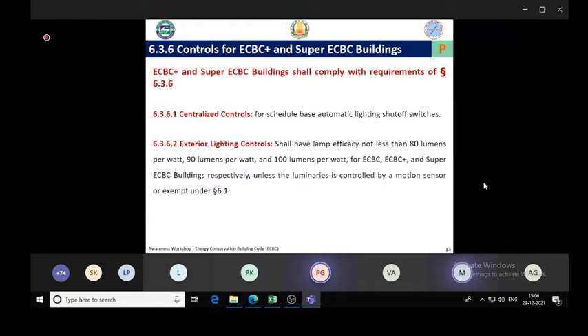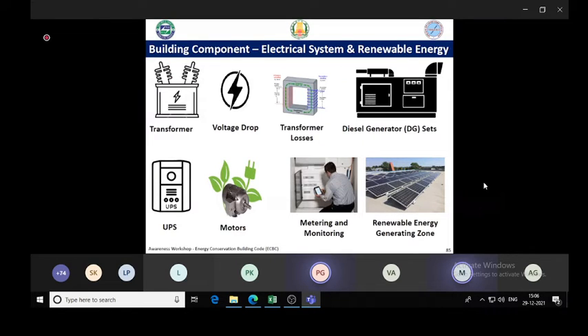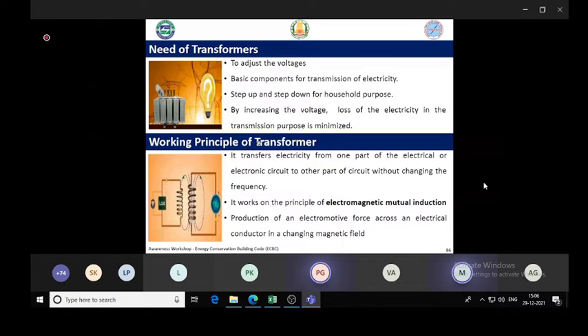Okay, so that was about the lighting section, and now the electrical section. In the electrical section, all of the requirements are mandatory. There are requirements for transformer, voltage drop, UPS, motors. We'll see them one by one. In transformers, the code mentions the maximum allowed losses for both dry type and oil type. There is a table given. So the efficiency of the transformer should be within the code requirement. For example, we should have a certificate of the transformer loss at 50% loading and 100% loading, and that should be less than the given values. So before you specify the transformer, you need to specify your loss at 50% and 100% loading.